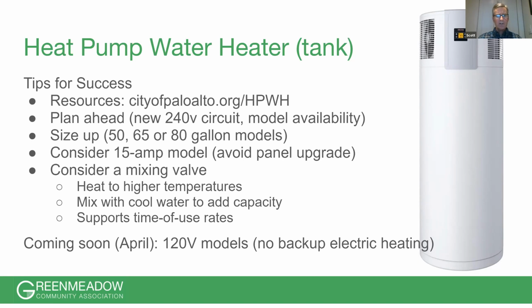There's another component to capacity, which is adding a mixing valve—many units already come with one installed. A typical water heater temperature is 120 degrees, which is for safety, but the water heater can actually generate higher temperatures. The mixing valve merges that hotter 140-degree water, or even higher, with cooler water to make it safe to use at 120 degrees. So essentially you have a larger capacity because you have this hotter water available.